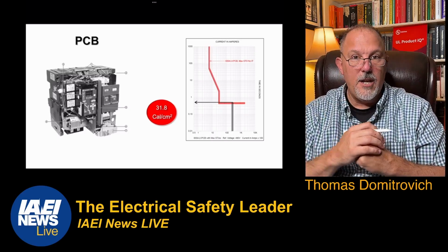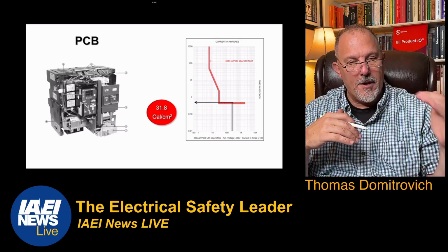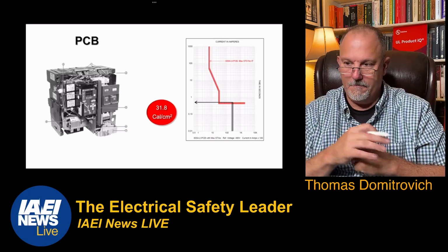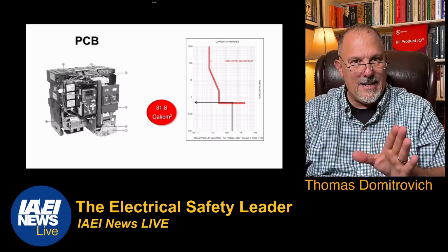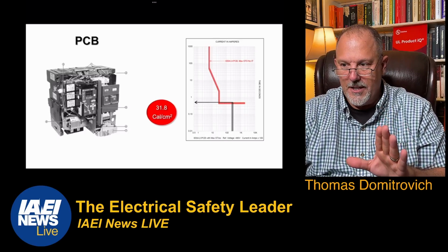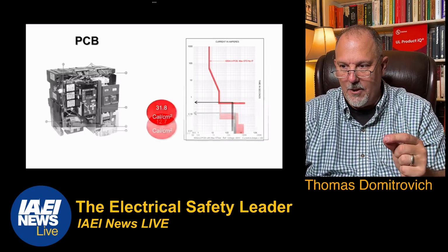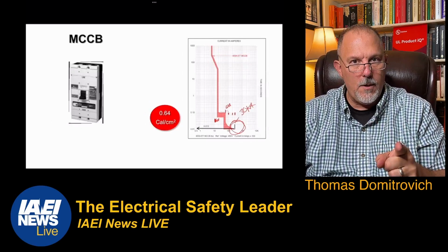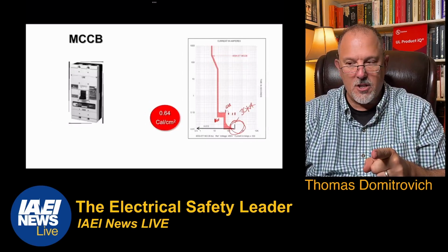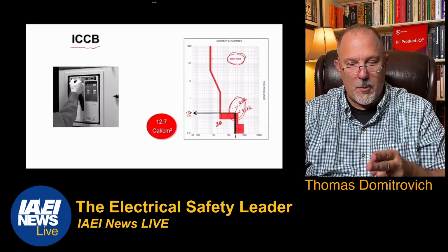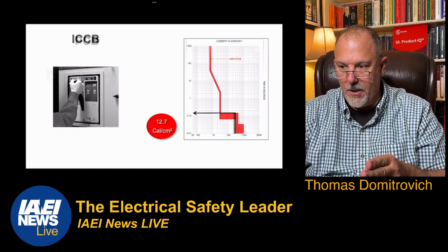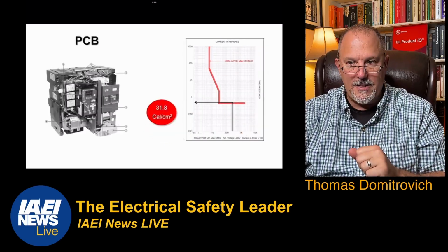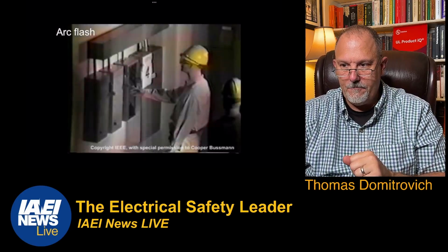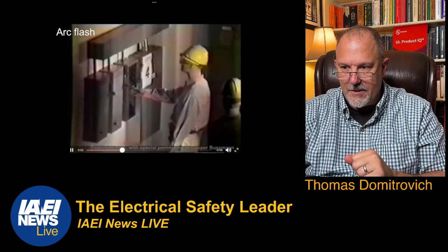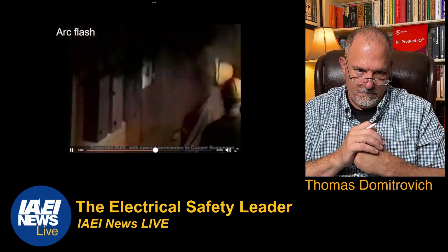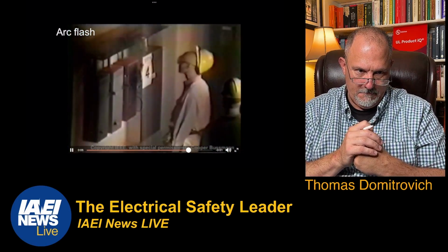You'll typically see these larger breakers up there at the service entrance equipment. So all I did between these three breakers is just add time. And I went from 0.64 with a 600 amp molded case circuit breaker, to 12.7 with an insulated case circuit breaker, to 31.8 with a power circuit breaker. We'll never trip that breaker. Now this is a series of videos.